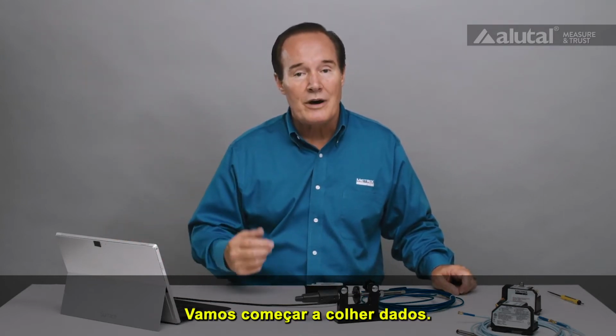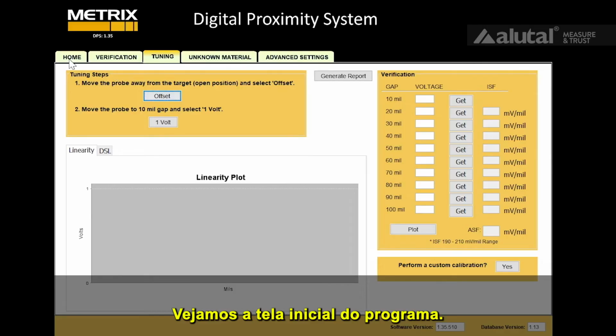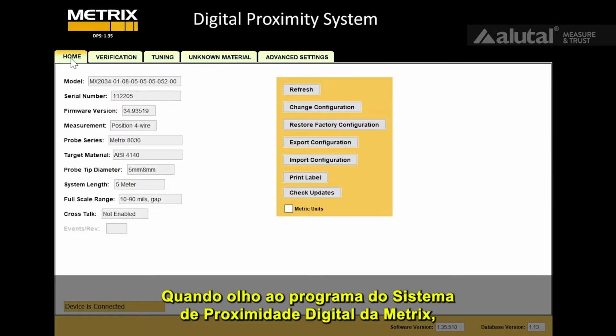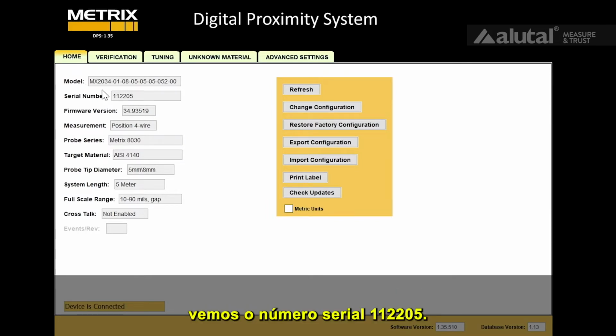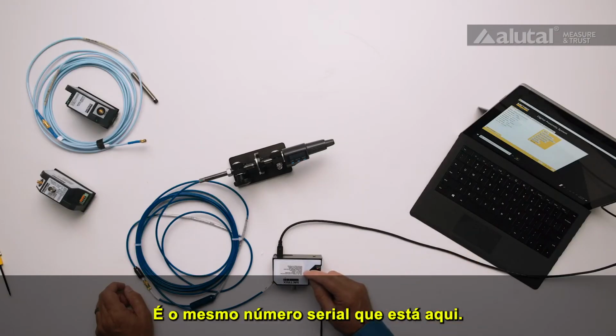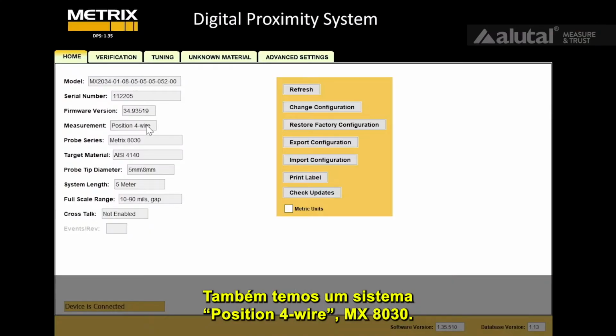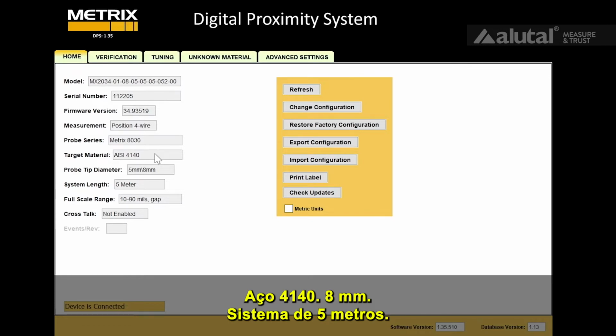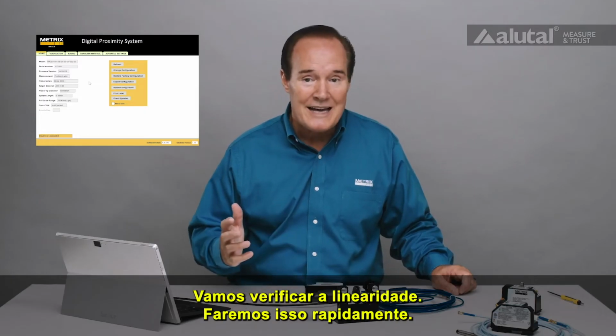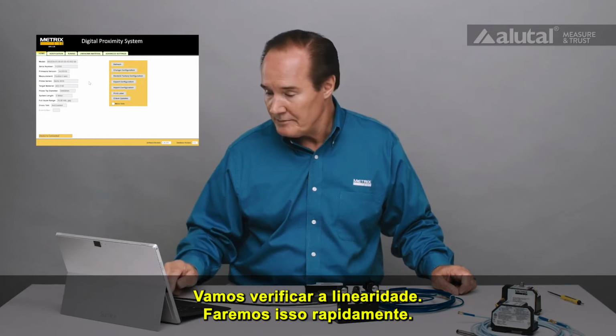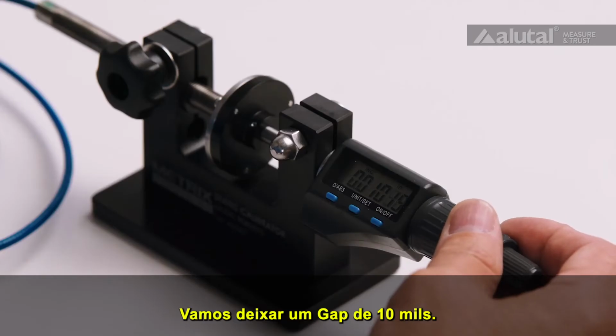What we're going to do is go ahead and take data. If I go to the home screen here, we'll start there. All right, so when I look at the Metrix digital proximity system software, we can see we have the serial number, and that's the same serial number that's here. All right, we also have a position 4-wire system, MX8030. It's 4140 steel, 8 millimeters, 5 meter system, and we're set for 10 to 90. So that's the setup, and we're going to go ahead and take data and check out linearity, and we'll do that quickly. We'll go ahead and gap it to 10 mils.